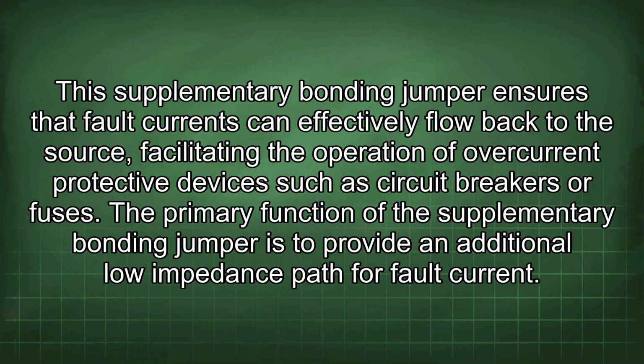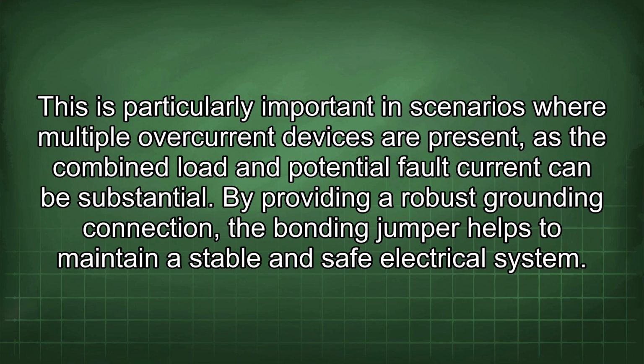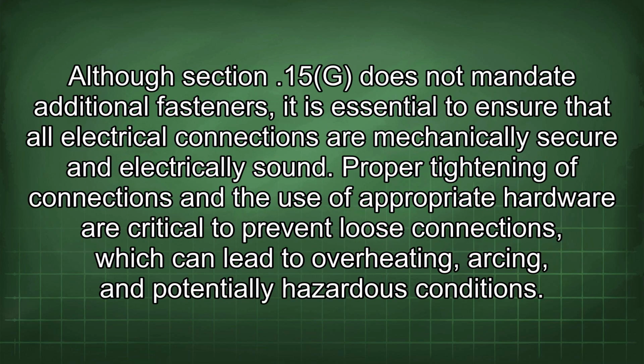The primary function of the supplementary bonding jumper is to provide an additional low impedance path for fault current. This is particularly important in scenarios where multiple overcurrent devices are present, as the combined load and potential fault current can be substantial. By providing a robust grounding connection, the bonding jumper helps to maintain a stable and safe electrical system.